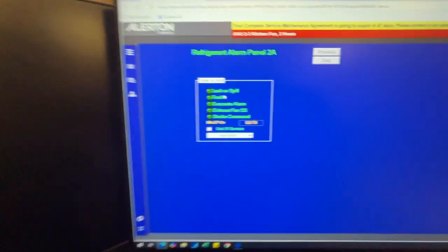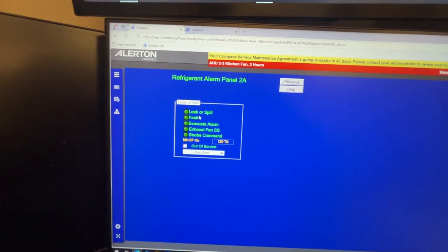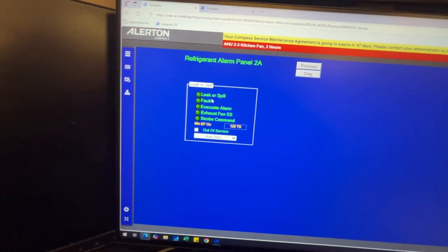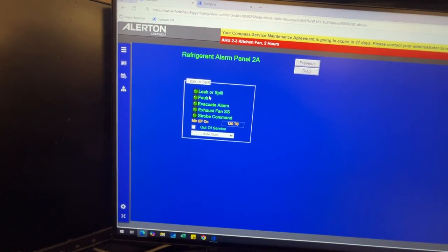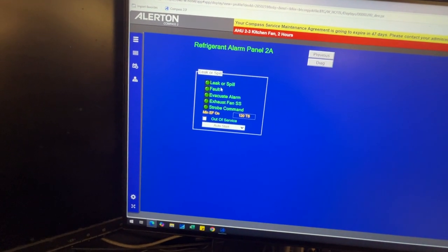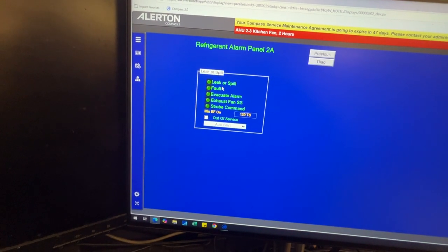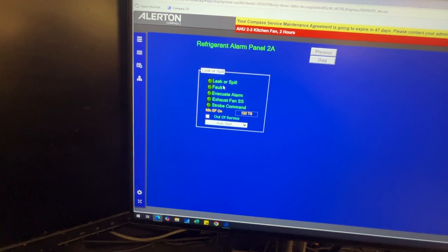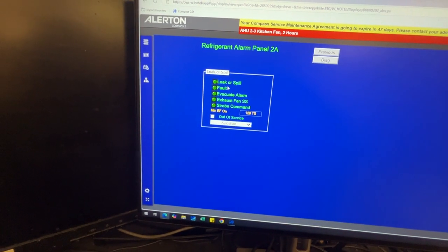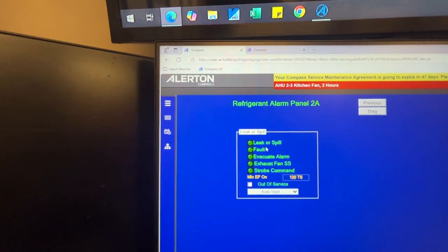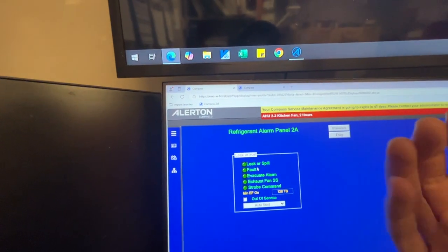Refrigerant alarm. So refrigerant alarm, this is important. We did set this up when I was here. We put the refrigerant alarm in in 2022. In 2021, when I got here in November, all of the tubes were rotted and crumbling apart, and it didn't work. Someone had turned off the refrigerant alarm. It had been off for years. So just make sure we stay on top of it. Once a month, they should be checking in on it.